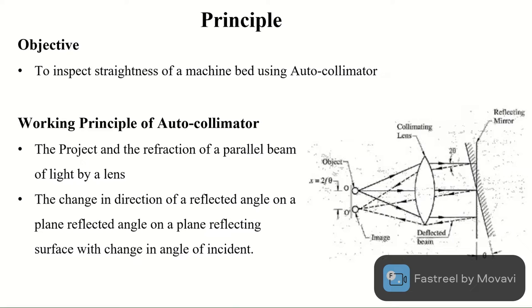I will explain the working principle of the autocollimator. The autocollimator works on two basic principles. The first one is the projection and reflection of a parallel beam of light by a lens. The second is the change in the direction of a reflected angle on a plane reflecting surface with a change in the angle of incidence.